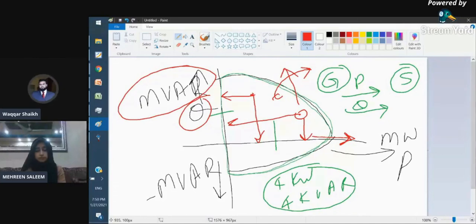What does underexcitation mean? Underexcitation relates to the lower region, this region. It means there are some elements in the network which are injecting reactive power into the network, like capacitor banks or long transmission lines. If you have an excess of reactive power in the network and it is not being used by inductive loads, that reactive power will flow back into the generator. Whenever these load flow situations come, we call it underexcited operation. Underexcited operation is not a normal operation.